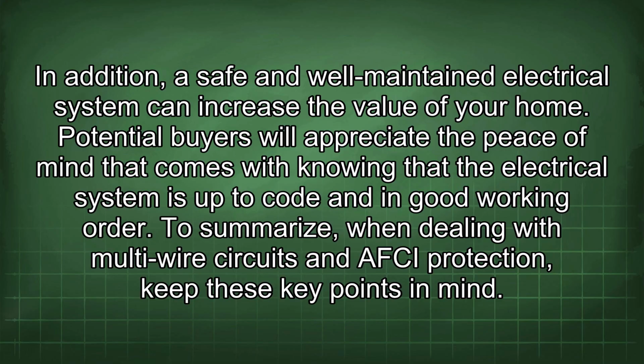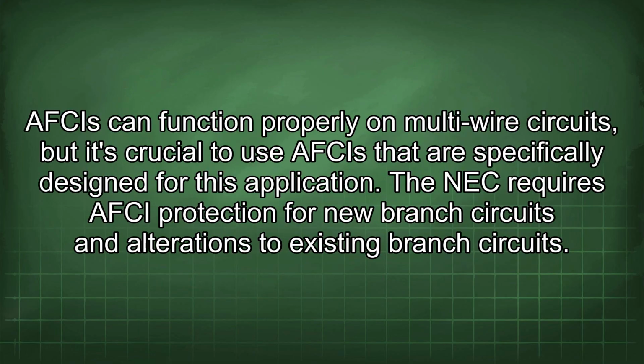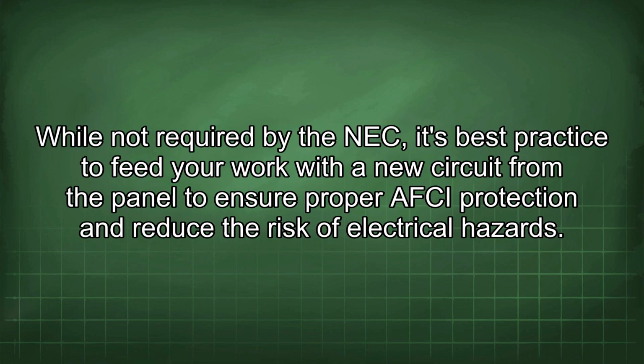To summarize, when dealing with multi-wire circuits and AFCI protection, keep these key points in mind. AFCIs can function properly on multi-wire circuits, but it's crucial to use AFCIs that are specifically designed for this application. The NEC requires AFCI protection for new branch circuits and alterations to existing branch circuits. While not required by the NEC, it's best practice to feed your work with a new circuit from the panel to ensure proper AFCI protection and reduce the risk of electrical hazards.